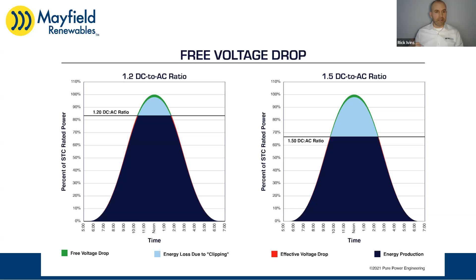Well, it's really about assuming that your array takes up the size of the field that it is. It's how many inverters do you really need. So by doing a higher DC to AC ratio, you're trying to get away with fewer inverters, fewer kW of inverters. So saving money on the price of the inverters, the price of the installation and wiring to the inverters, the monitoring, the ongoing monitoring costs of the inverters, ongoing O&M to service each one. So it's more about trying to eliminate the amount of inverters and all the savings that come along with that.